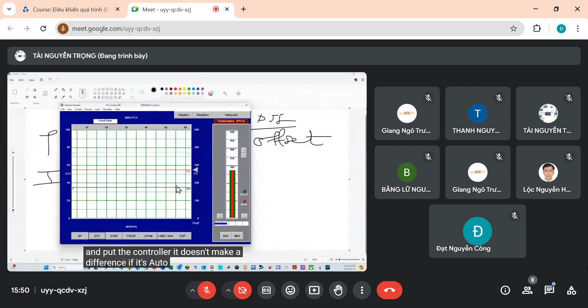In this instance, I'm just going to say control, and my control option is going to be integral only. Let's put that one into the controller itself. I'm then going to put the controller - it doesn't make a difference if it's auto or manual, it doesn't make a difference at all. I'm going to put in the tuning parameter of 0.04. Okay, let's put that in.